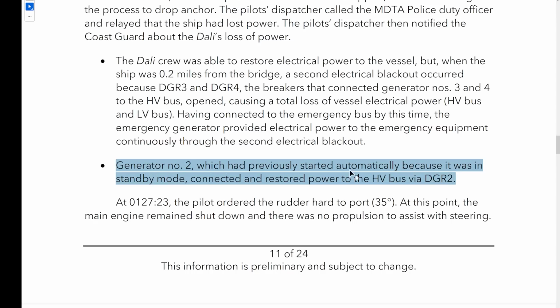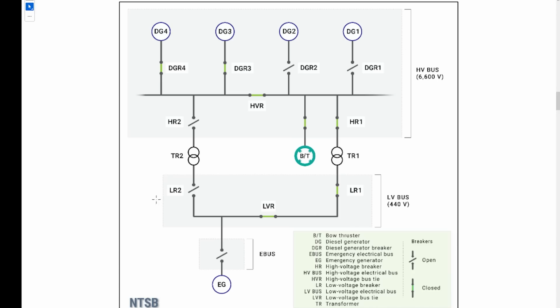Generator number 2, previously started automatically since it was already in standby mode, connected and restored power to the high voltage bus. Coming back to the electric diagram, remember DG4 and DG3 are still open and out of the equation. Diesel generator number 2 was online, kicked in, and this switch closed, now providing power to the 6600 volt bus, so the ship has its power restored once again.